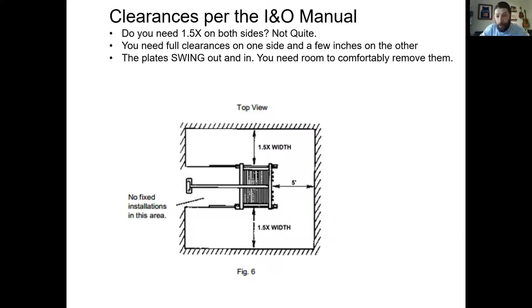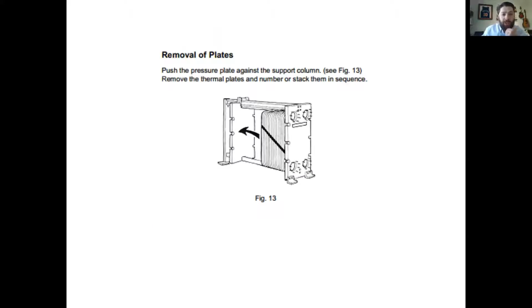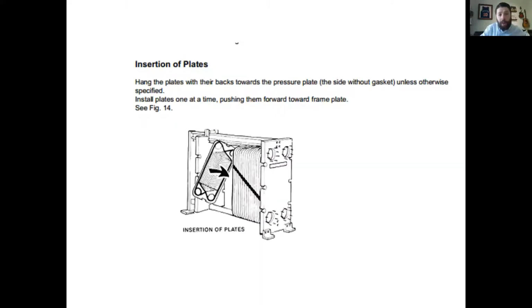You need 1.5 on one side, and you need a few inches on the other side because the plates swing out, and you're picturing a rectangle. They connect to that top carry bar, and they swing. So when you're removing the plate, you push the pressure plate all the way back against the column, as seen in this picture here, and you start removing the thermal plates. Now you want to stack these, you want to keep these in sequence. It's very important. Not every plate in there is the same. I'm going to repeat that. They're not all the same. Keep them in order.